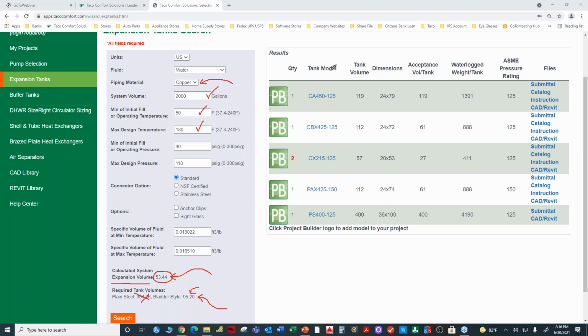So let's go through and look at the first. The software has made this selection of CA 450, which has a physical volume of 119 gallons. Well, that's greater than the 95, so it meets that criteria. The acceptance volume, this is how much water the bladder can hold, 119. And whenever the tank volume is equal to the acceptance volume, we call that a full acceptance tank. That's how you can easily tell from the selection software that you have a full, that looks like an E, sorry about that. Let me scribble that. So we want to say that that's a full acceptance. So I'm going to say FA, full acceptance. And that's because the tank volume is equal to the acceptance volume. So that's the first one.